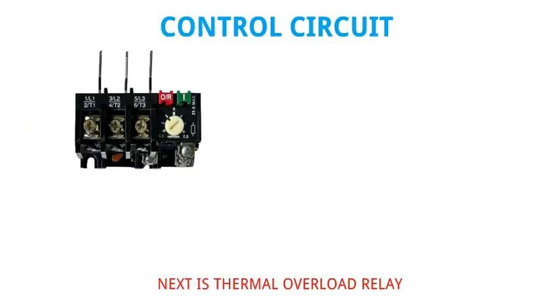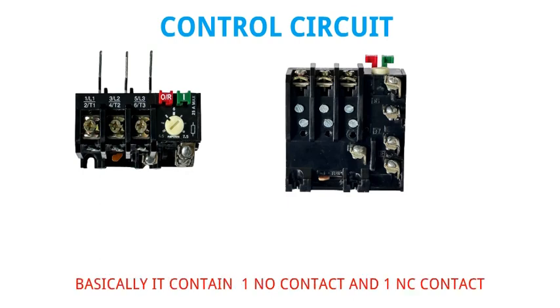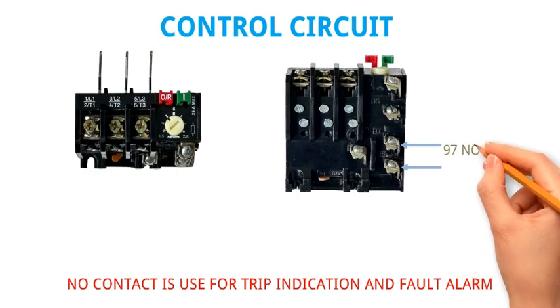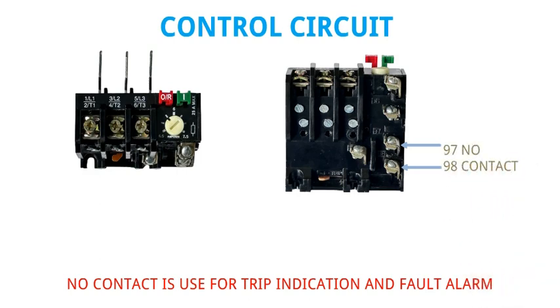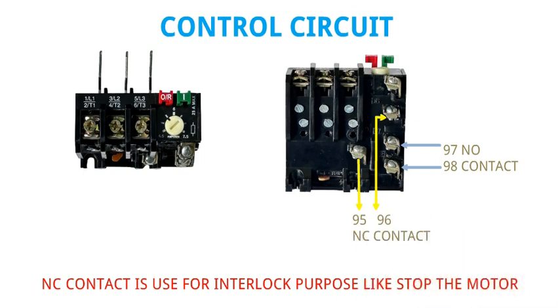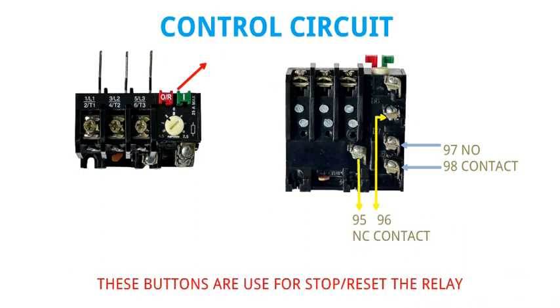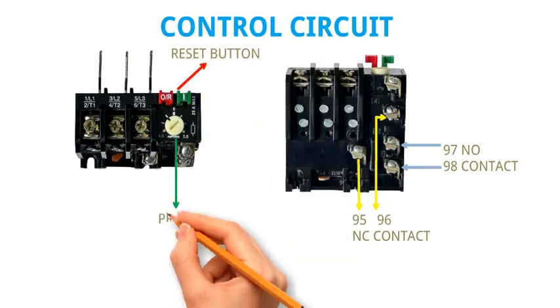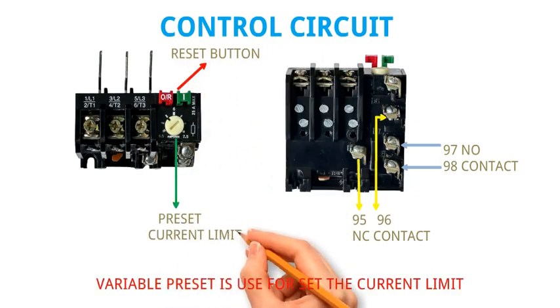Next is the thermal overload relay. It basically contains one NO contact and one NC contact. The NO contact is used for trip indication and fault alarm. The NC contact is used for interlock purposes, such as stopping the motor. The buttons on the relay are used to stop or reset it. The variable preset is used to set the current limit.